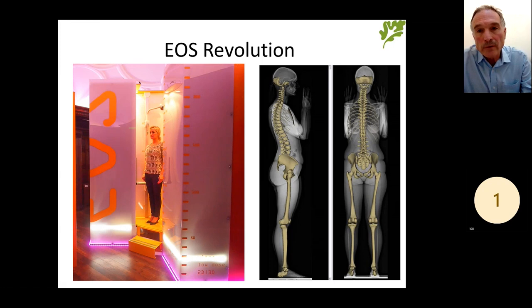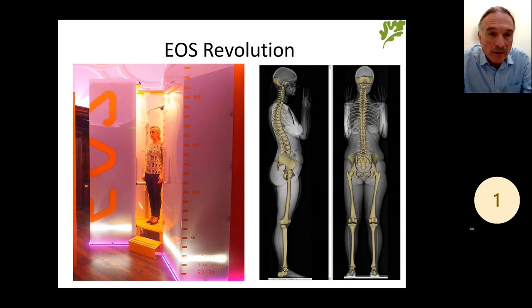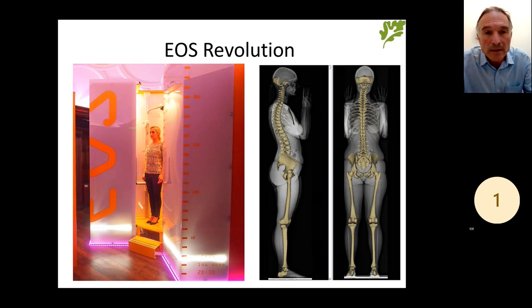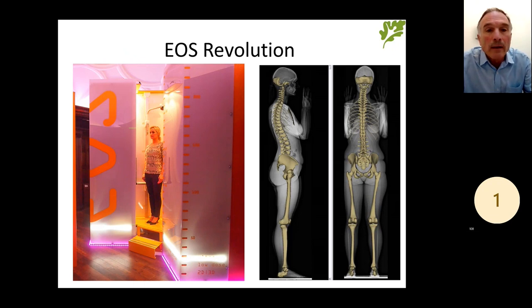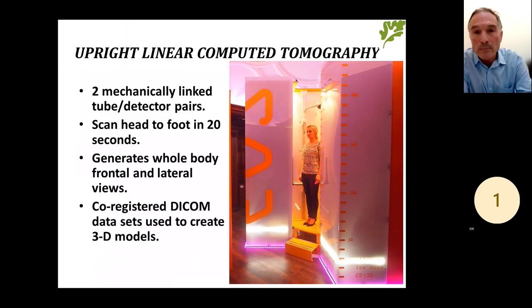The ability to look at this in real time and weight-loaded positions moved forwards a long way with what I call the EOS revolution. You can see here on the left an EOS machine, which is a fairly cumbersome bit of kit. Although it produces images that look like X-rays, they're not to be thought of as X-rays. These are actually two linear scans which are connected together and processed to produce a 3D model of the standing skeleton. It takes about 20 seconds to complete the full scan. We call this upright linear computer tomography.